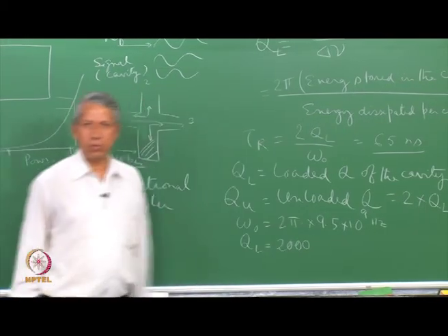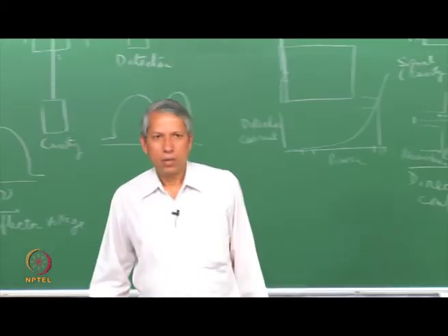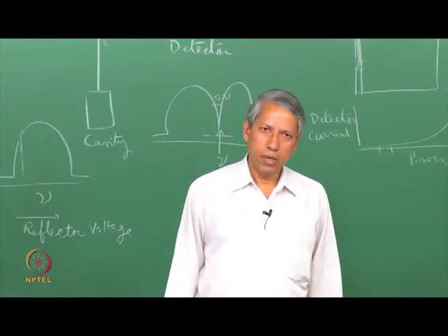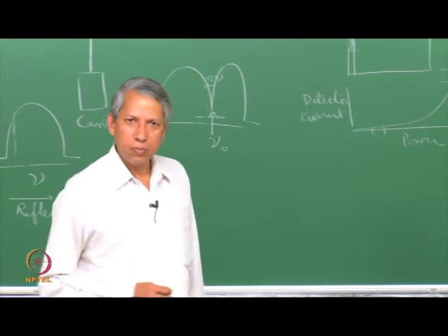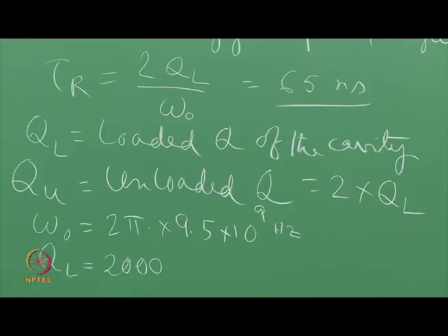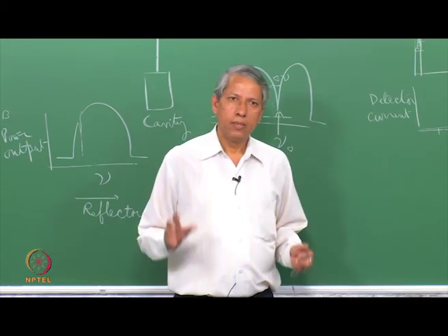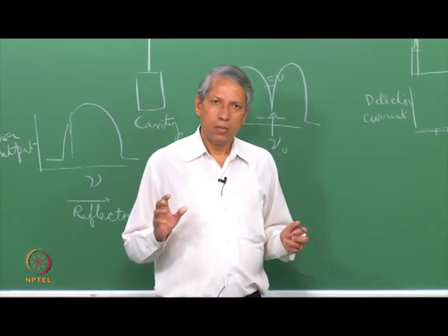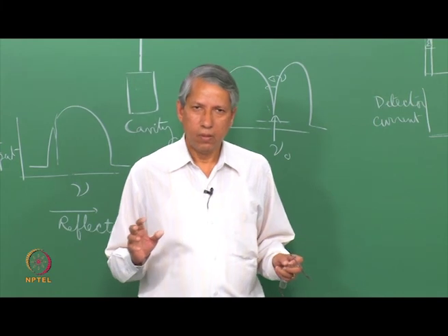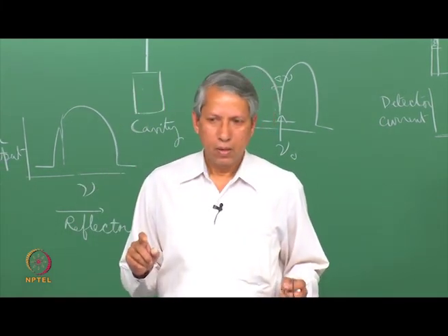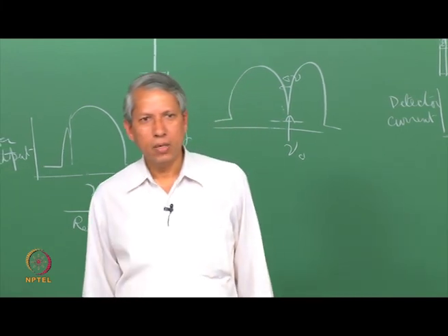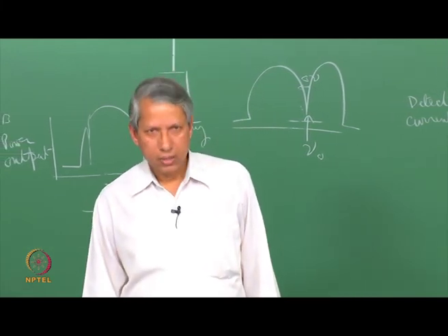So, here the higher the Q, the longer it becomes. That is the same as what we have said, that if the cavity Q is high, then it resists the change of microwave power inside the cavity. With this, we have basically given the overall appearance of a direct detection EPR spectrometer, and in the next lecture we will see how we can improve the sensitivity of this.